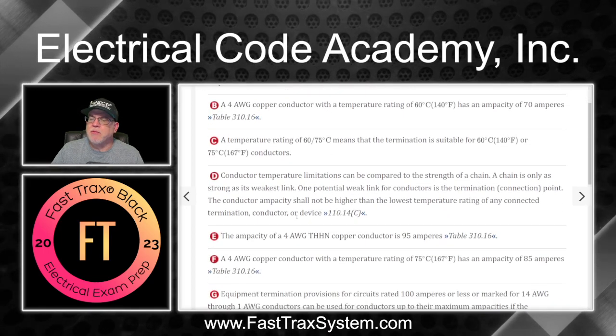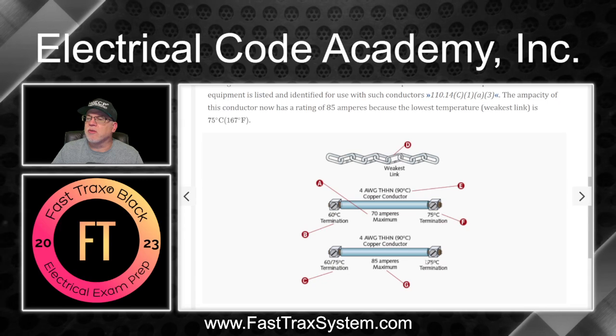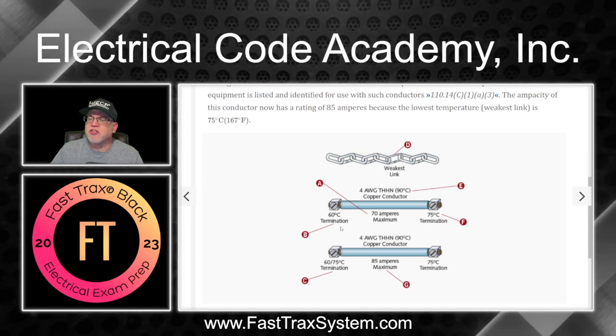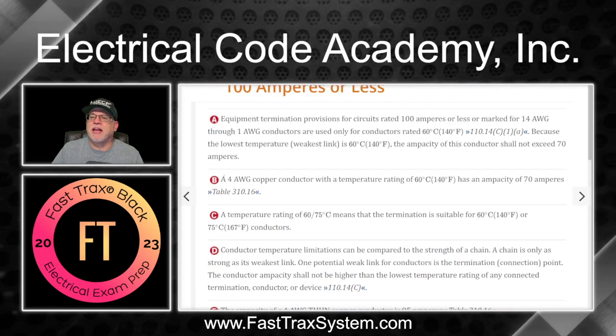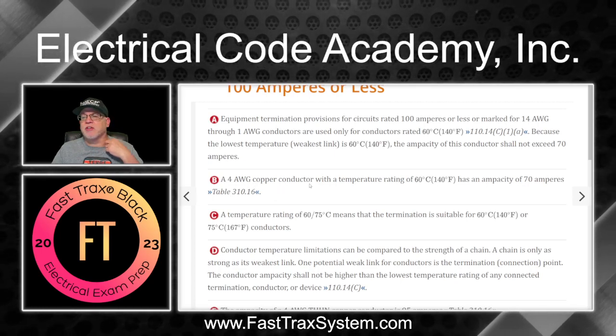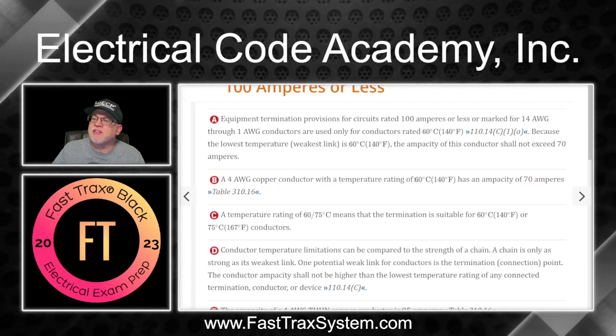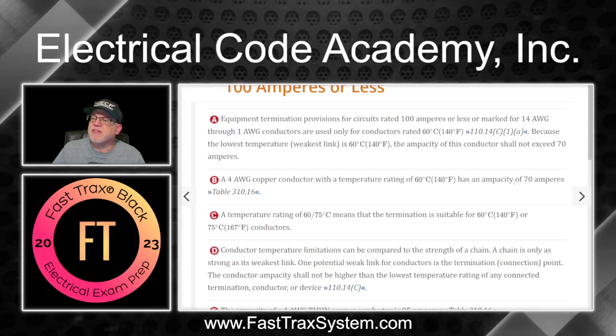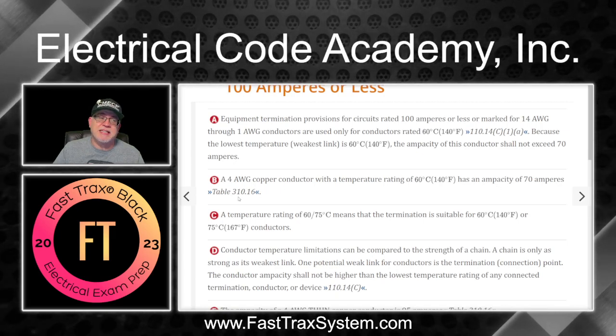Now, B, which is pointing right here, where's B at? Right here. That's the terminal issue. It's telling you that a 4 AWG copper conductor with a temperature rating of 60 degrees C has an ampacity of 70 amperes. And again, that would be in Table 310.16.